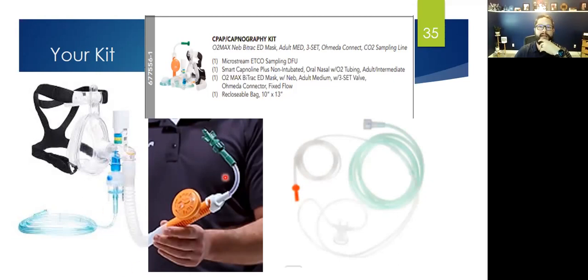Obviously, there's friction loss and such, but the next thing I want to point out is that your system uses an actual vent tube. What's interesting here is that there are many different units out there that just use a standard oxygen supply. What I want to challenge you guys with is this: if hospitals knew they could get away with using oxygen supply tubing to do this, they probably would, because it's significantly cheaper, right? But you ultimately need that extra space to deliver proper flow to the patient so they can actually breathe on this device without over-breathing it. I'll go into that in a second too. So there's an actual vent tube that goes up to your unit. That's where, like I said earlier, the oxygen and air come in, the anti-asphyxia valve closes, and it goes into the patient. They're able to breathe, and on exhalation it goes through this exhalation valve here. What I want to show you guys is this, so make sure you're paying attention right here. This is your exhalation valve and PEEP, right?